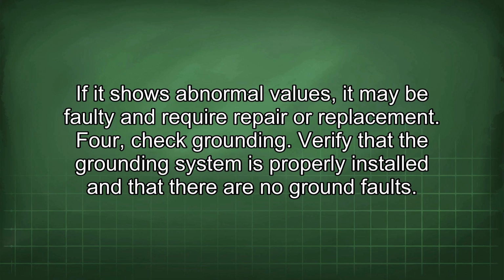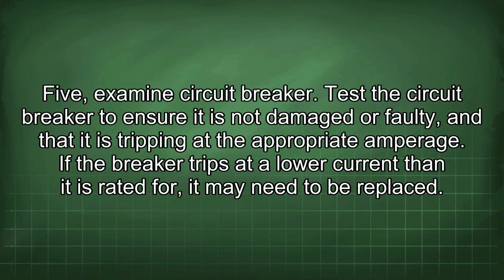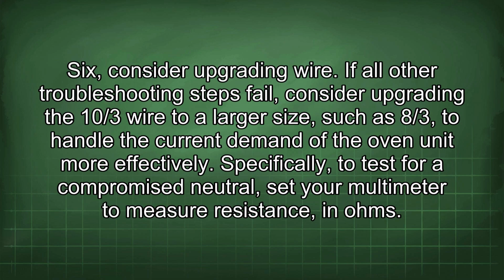4. Check grounding. Verify that the grounding system is properly installed and that there are no ground faults. 5. Examine circuit breaker. Test the circuit breaker to ensure it is not damaged or faulty and that it is tripping at the appropriate amperage. If the breaker trips at a lower current than it is rated for, it may need to be replaced. 6. Consider upgrading wire. If all other troubleshooting steps fail, consider upgrading the 10/3 wire to a larger size, such as 8/3, to handle the current demand of the oven unit more effectively.